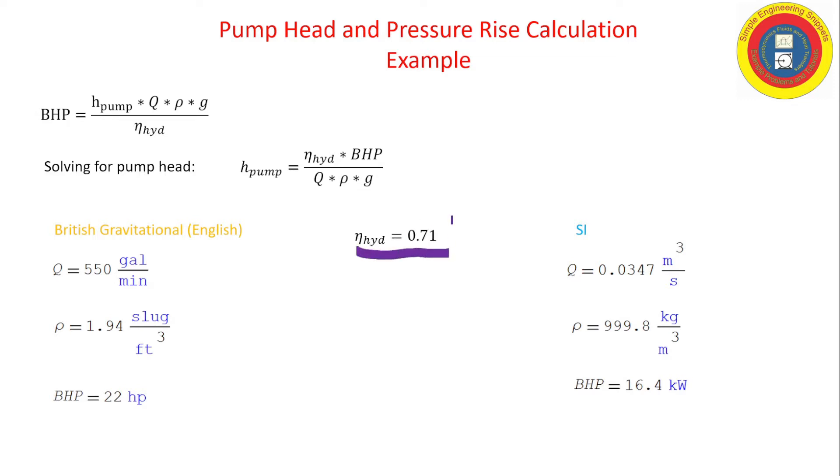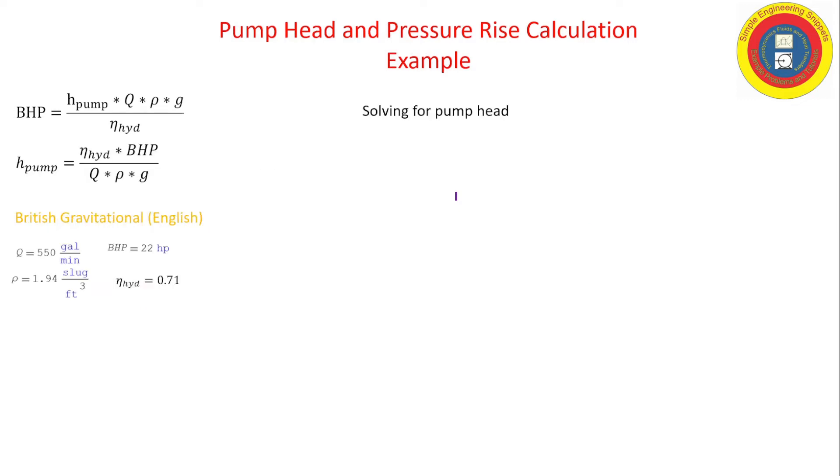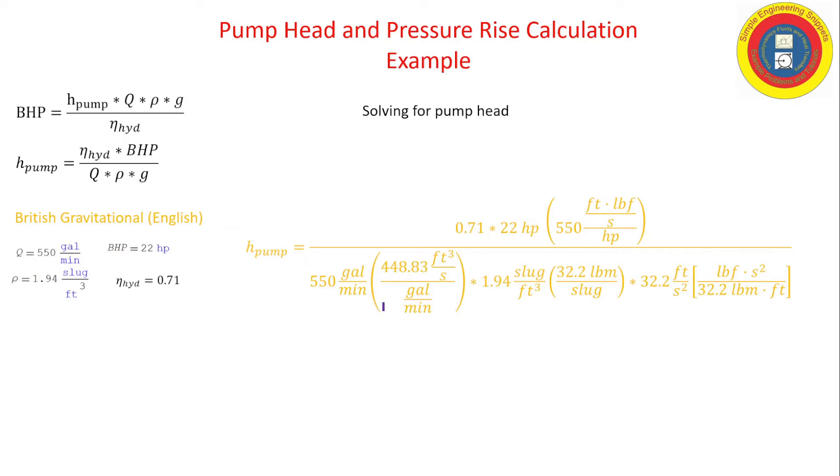The hydraulic efficiency does not depend on the system of units; it's 0.71 for both systems. Okay, so let's go ahead and work with the English or British gravitational system of units. We plug in our parameters with units, and as you can see, as is typical, we have a lot of conversion factors we have to go through, including a one over g sub c to get the units to work out. But it is doable, and when we're done we get that the head of the pump is 112 feet.